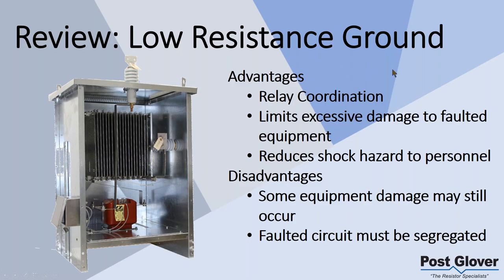One of the ways we actually do relay coordination, and the reason why it works: if you have a solid ground system, let's say, you're going to have potentially thousands of amps of ground fault current. If you have a resistance grounding system, you get to define that value, right? So let's say you have 400 amps of let-through current. When you get a ground fault, you're getting 400 amps versus a few thousand.